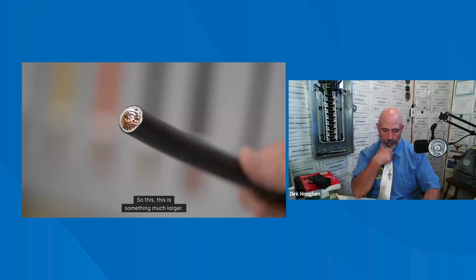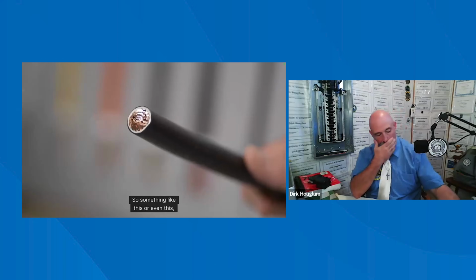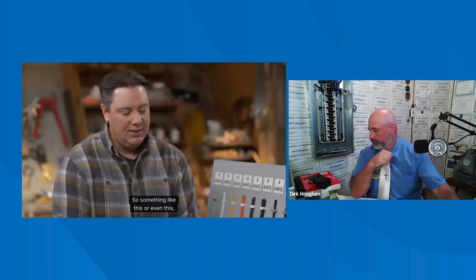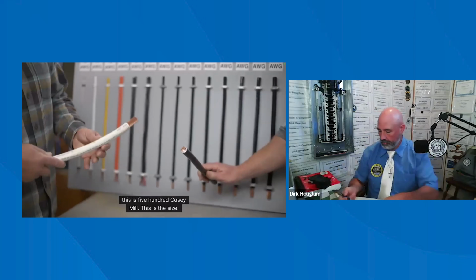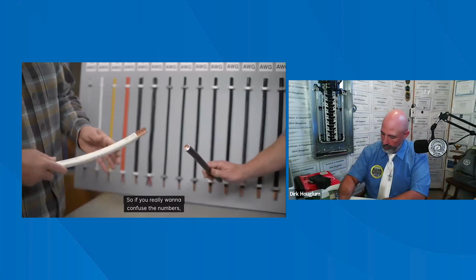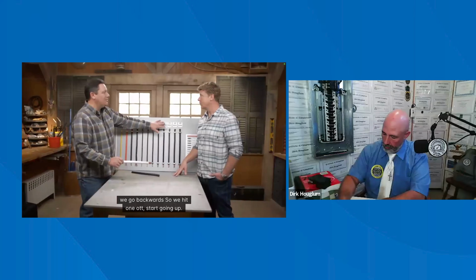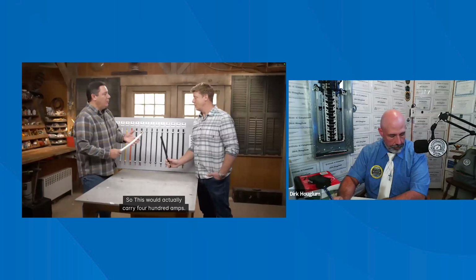Or this? So this is something much larger. So something like this, or even this is 500 kcmil. This is the size. So if we really want to confuse the numbers, we go backwards till we hit 1 aught, start going up, and then we go metric. kcmil, oh, the letter K? Yep, 1,000 circular mils. Gotcha. So this would actually carry 400 amps.